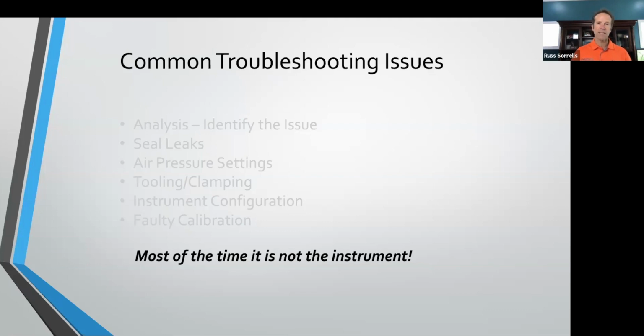You just run a self-test, and it will do an analysis on the manifold inside the instrument to determine if there is a fault. And 95+% of the time, probably closer to 99% of the time, I get the green light and it says the instrument is good, the self-test passed. And of course, upon identifying that, we start into this analysis process, identifying where the issue is. Is it seals? Is it pressure? Tooling, clamping, instrument configuration, things such as that.